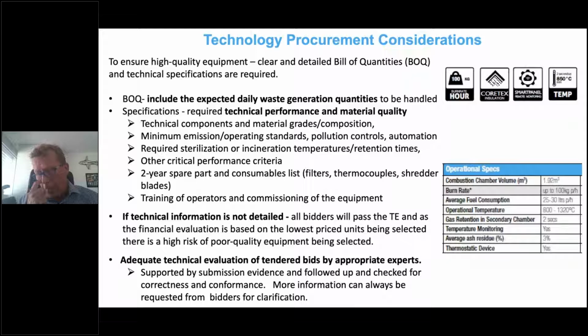We would also stress that you should include in any procurement exercise spare parts for a minimum of 2 years, and the consumables that technology will use, such as filters for an incinerator, and thermocouples which measure and read out temperature to the control panel. Those are robust but will last less time than the unit, so you'll need to replace them during its lifespan. Also shredder blades—in an autoclave or sterilizer these wear out quickly because of the heavy shredding work, so you may need spare high quality blades for that.